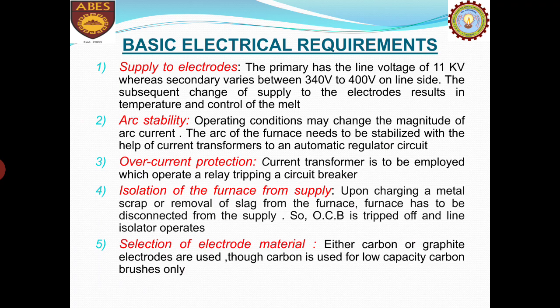Now the stability of the arc for a fixed gap is further increased due to high reactance of the furnace transformer. Now if I talk about the overcurrent or ground or leakage fault protection, we know that except for a momentary short circuit, the furnace is not supposed to draw overcurrent. By overcurrent I mean more than the furnace rating current. So for this purpose, the current transformers need to operate a relay circuit tripping the oil circuit breaker.